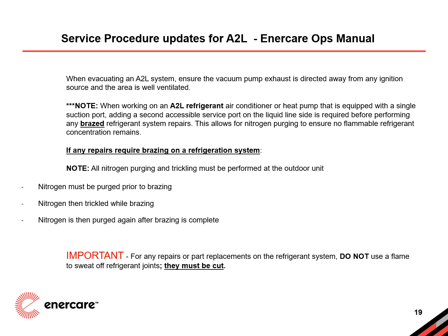Furthermore, when working with A2L refrigerants, it is essential to take precautions to minimize ignition risks during evacuation. Always conduct evacuations in well-ventilated areas and ensure the vacuum pump's exhaust is directed away from any potential ignition sources. When making repairs, avoid using a torch to unsweat joints or fittings. Instead, cut into the piping system to safely remove the damaged section. Then use nitrogen as a purge gas while brazing the system back together to prevent oxidation and maintain system integrity.